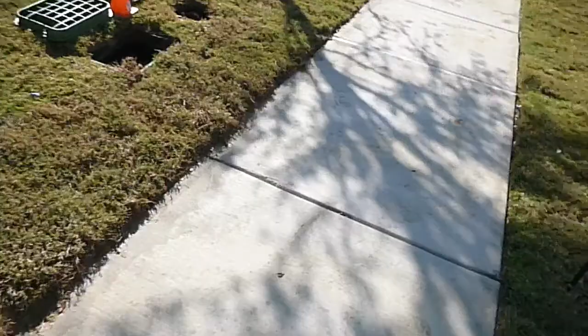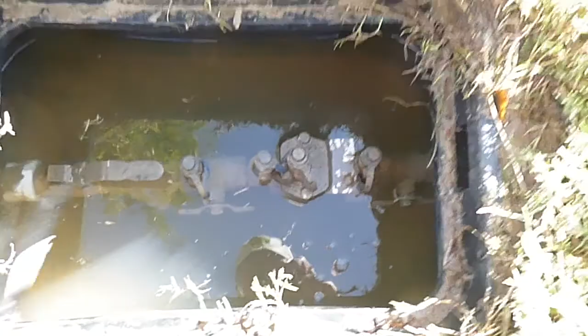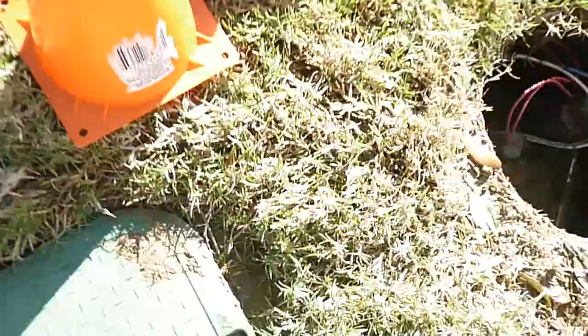Over here, across the parkway sidewalk, is the lawn sprinkler system. I open this irrigation box up. That's a valve - this is your check valves and your isolation valves for the handles, and you've got the covers on them. I can't tell whether this box has been excavated and covered with a layer of gravel to keep erosion from coming in. That's good practice for this box, and also good practice for the meter box, though it's not required there - it is required on this one. Another thing that's required, oh, you have it: this is the main shutoff valve for the lawn sprinkler system, and these two valves are service isolation valves. So this box has everything it's supposed to have, assuming there's gravel underneath it.